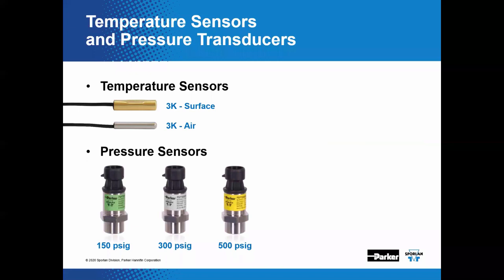That's pretty neat. With any of these controllers, choosing the right sensors is key. Sporlan offers a number of temperature sensor models. Here are just 2 examples. The 3K surface sensor, the 3K air sensor. We also have the 2K version as well. The Sporlan 3K sensor can be identified by its brass sensing tip. That's the case in this particular example. Both these sensors will work with the Kelvin 2 series controller. We've found the 3K sensor versus the 2K to be pretty robust, and it's recommended over that. We also offer a 10K sensor as well.